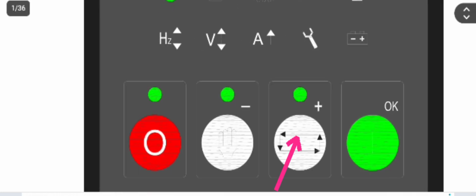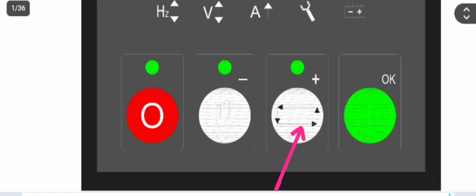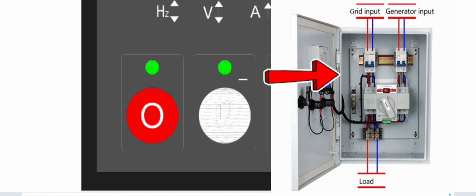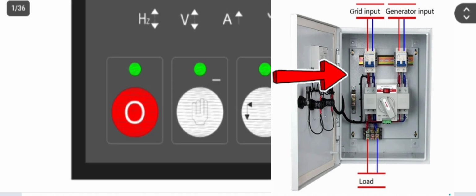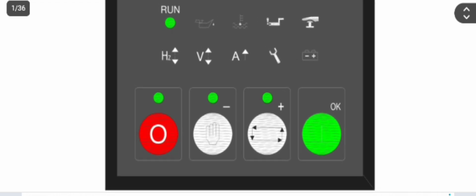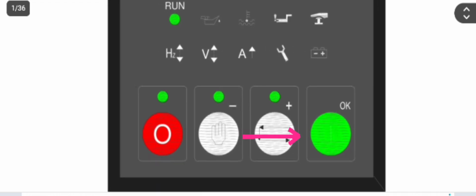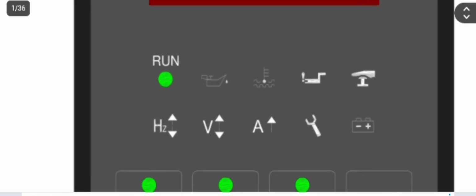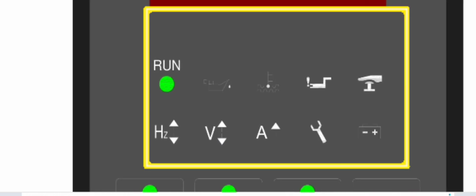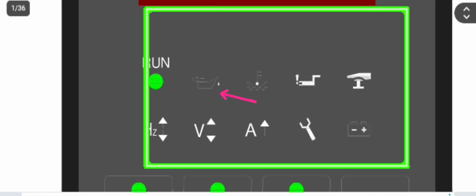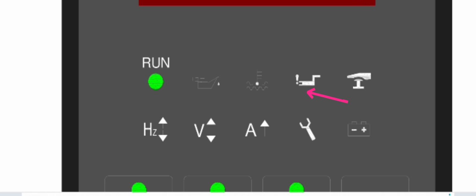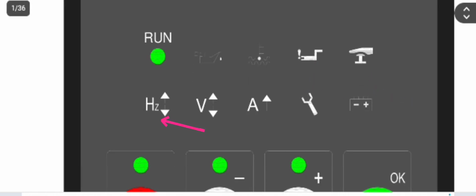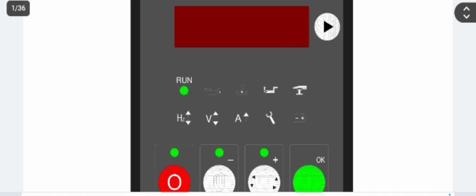And this one, the positive button, is used for automatic operation. If the generator is connected with the ATS control panel, you can also run your generator automatically. Finally, the green button is used for starting. As you can see here, we have some symbols: run, low oil, high temperature, engine fault, emergency push button, frequency, volt, hour, ampere, and also the setting, and the last one is battery. These can monitor these safeties for you.